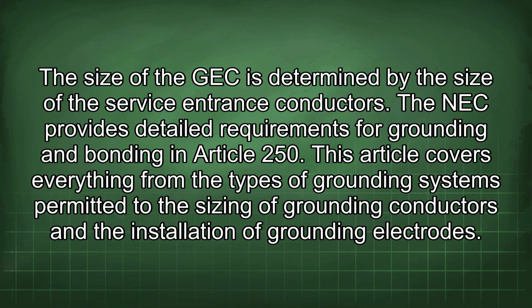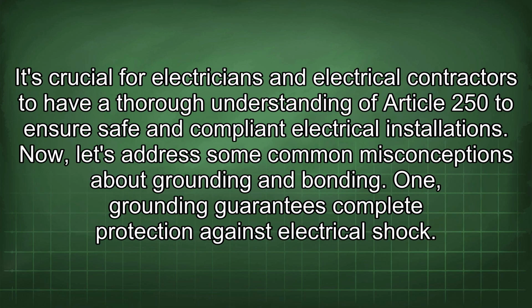The NEC provides detailed requirements for grounding and bonding in Article 250. This article covers everything from the types of grounding systems permitted to the sizing of grounding conductors and the installation of grounding electrodes. It's crucial for electricians and electrical contractors to have a thorough understanding of Article 250 to ensure safe and compliant electrical installations. Now let's address some common misconceptions about grounding and bonding.